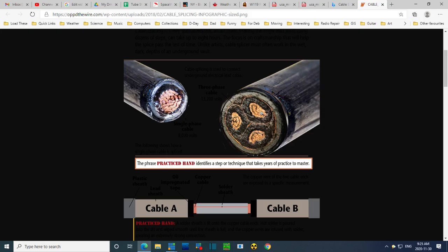You really want the electric stress to go straight through the paper, like from here to here, straight through the sheets of paper. Many, many sheets of paper lapped in here. But if somehow you get the electric stress traveling this way, over the surface of the paper, it acts very differently and you can get problems. Plus, right in the center of the cable, it's a construction nightmare, if you like. It's not uniform in here.